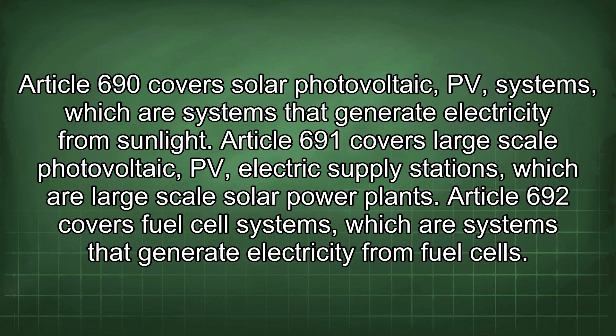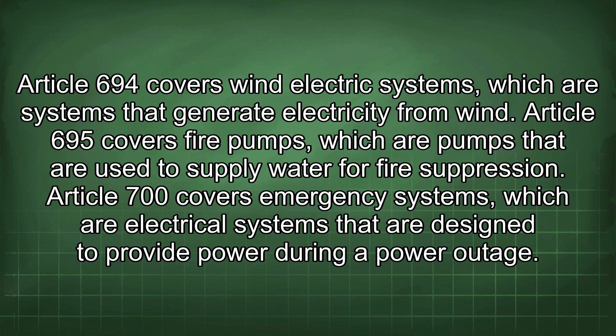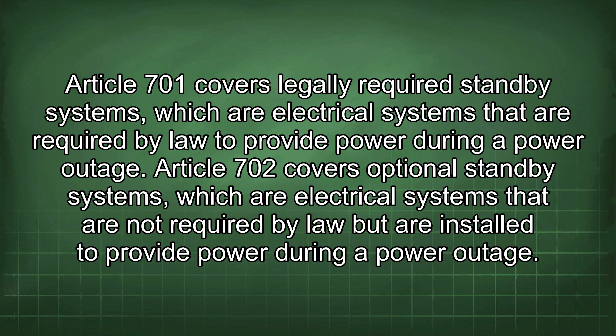Article 695 covers fire pumps, used to supply water for fire suppression. Article 700 covers emergency systems, electrical systems designed to provide power during a power outage. Article 701 covers legally required standby systems, required by law to provide power during a power outage. Article 702 covers optional standby systems, not required by law but installed to provide power during a power outage.